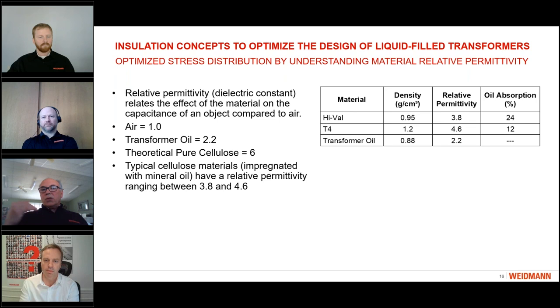So in that case, we're able to put more of the stress in the solid insulation because we have a higher relative permittivity liquid. And when we share this presentation, there are some references. There was a paper that I actually wrote, and it's in the references that talks about that. Okay, Tom, and just one particular specific as you're talking about that, about replacing mineral oil with natural ester, with the higher permittivity, and it's therefore closer to that of paper, is there an advantage or disadvantage relating to that?